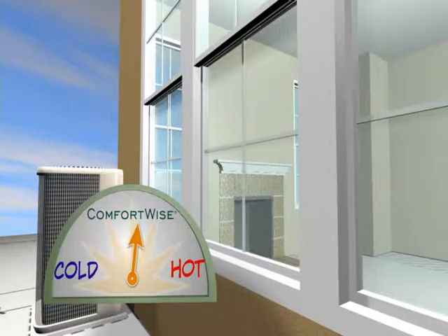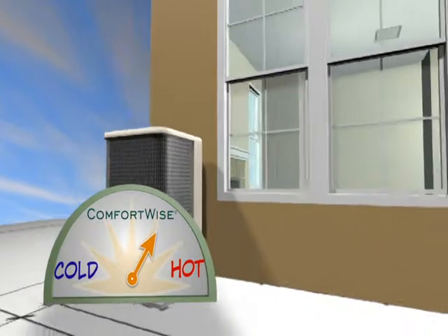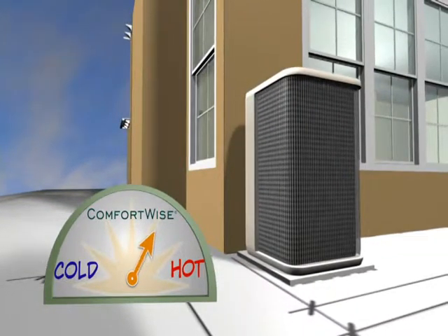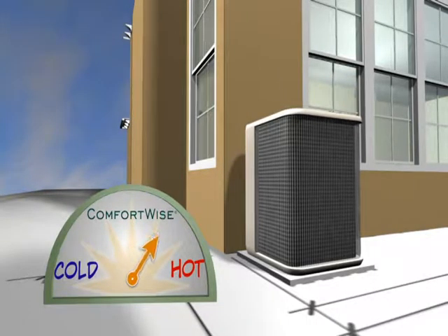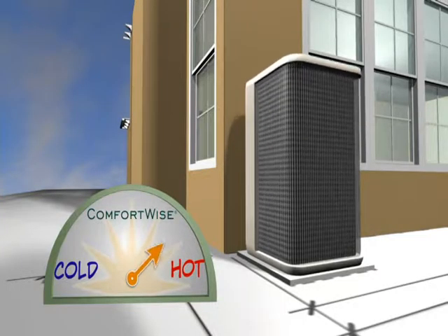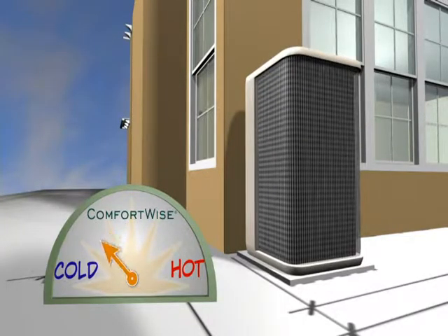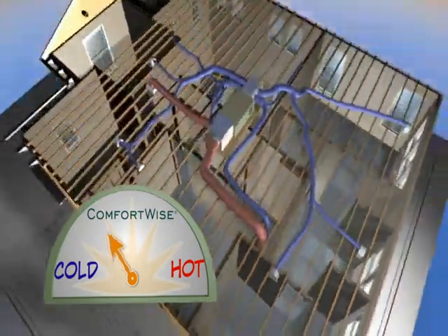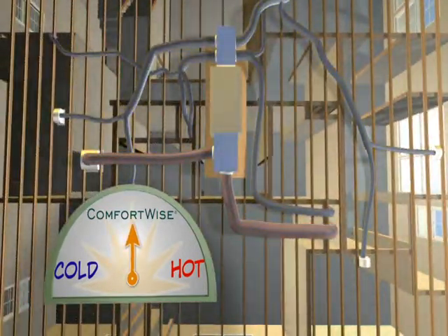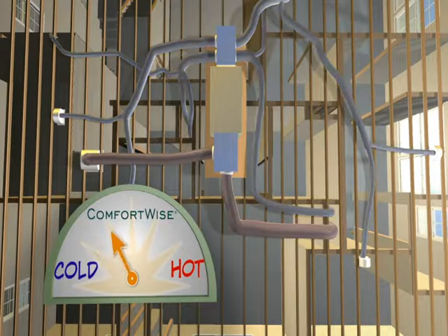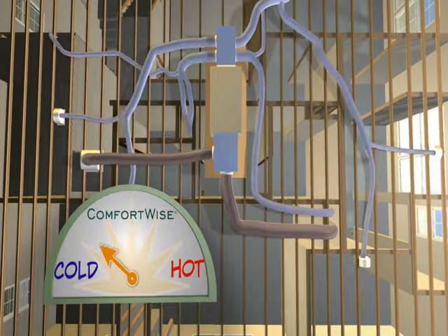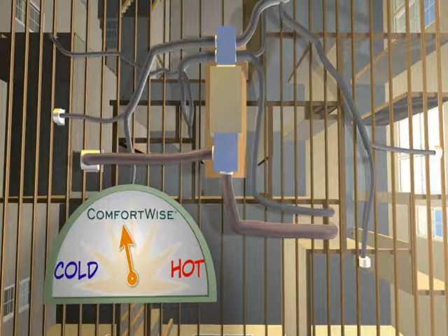But later in the morning, it's just getting too hot outside, so air conditioning becomes the only way to get back to the comfort level. Two things about air conditioning: first, the unit must be the right size. Too small and it can't keep up on the hottest days, running continuously. On the other hand, an oversized unit isn't good either—not just because of the added expense. Too big and it has a tendency to cycle, constantly turning on and off, delivering unwanted blasts of cold air, and it also shortens the life of the equipment.